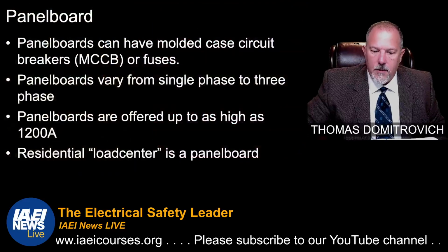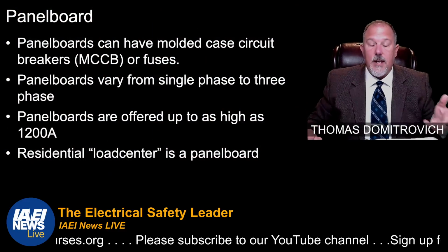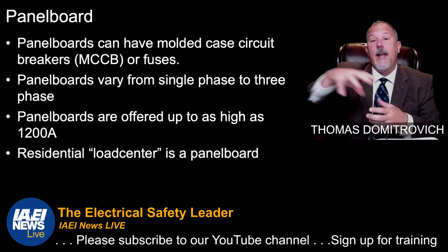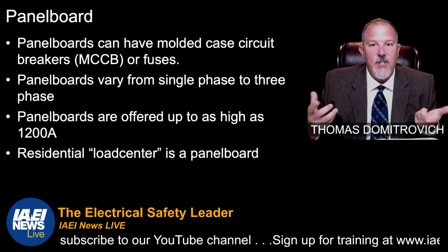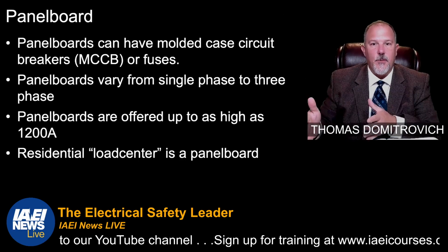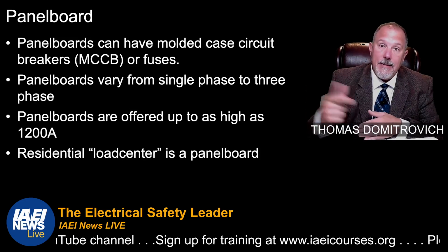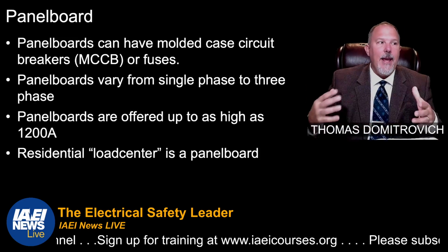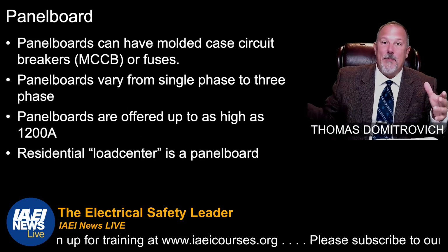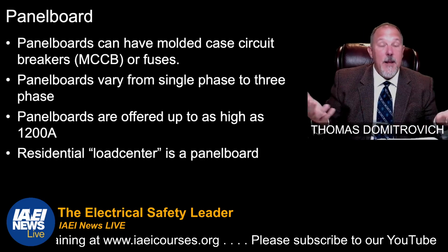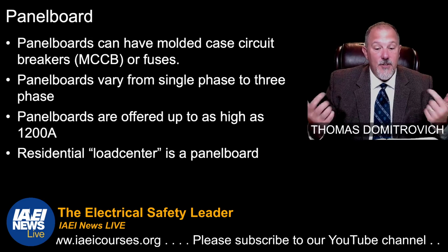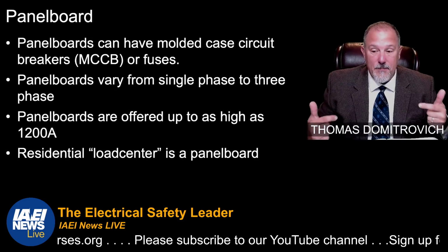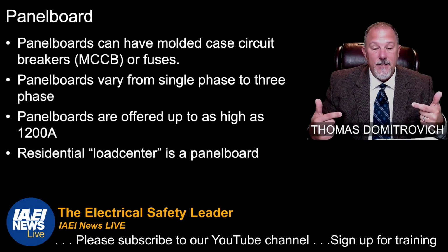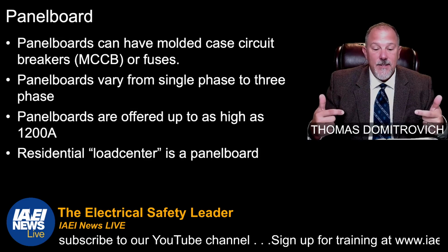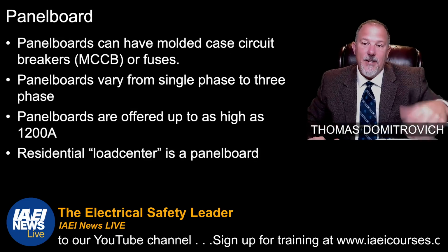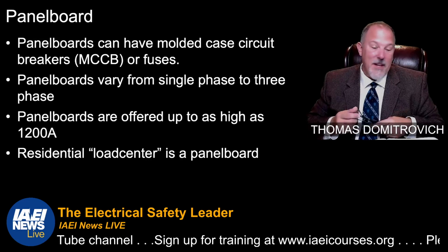All right, 408.38. Now let's talk about it. So panel boards can have molded case circuit breakers and/or fuses. You're not going to see an insulated case circuit breaker or a power circuit breaker inside of a panel board. It would be kind of hard to fit those big breakers inside this panel board, but panel boards do go up to 1,200 amps. Think about that. That's pretty high. And I know there's a term, load center, that a lot of us use.